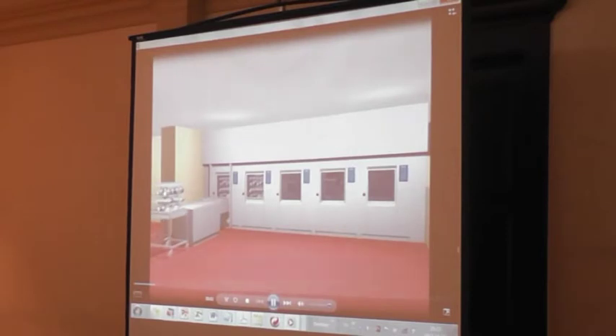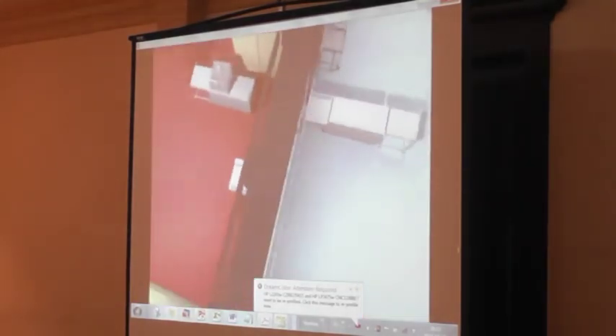Here we see the wash cart with the instruments - we put it here. This one is normally very long and can hold a lot of wash carts, and the shuttle brings the wash carts to the empty washers, automatically loading them in. It can even know what process to run - it can scan for that. So we wash for maybe 30 to 45 minutes depending on the program, then it goes to the packing area, goes down, and the shuttle knows that and collects items. No hands touch it here - it's fully automatic, and it's put out on the conveyor belt, which can be very long, up to 7 meters, holding a big buffer. So it can buffer, and if you go for a coffee break, it will move in and move out as distance - that's quite a nice function.